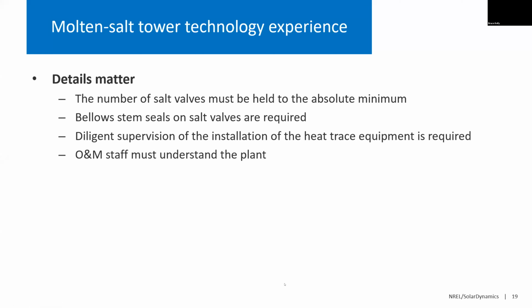And regarding heat trace, there's 10,000 ways to do heat trace wrong. There's one way to do it right. Heat trace installation needs to be overseen by someone who's gone through this before and can make sure that the heat trace cables, thermocouples, and every other process control element of the heat trace system is installed properly. Heat trace sounds ordinary, but unless it's done right, it's just a source of endless grief in a project.